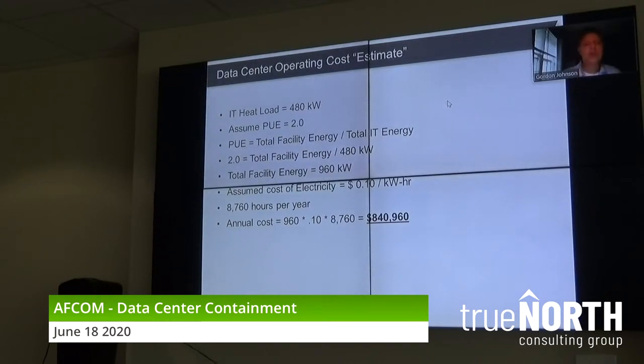So you also know how many hours there are in a year. So if you look at my final line, if you take your IT heat load, which was 480, multiply that by your PUE, so in this case, 960, times 10 cents a kilowatt hour times 8,760 hours in a year, that's the cost to operate this data center. And again, if you've provided me those numbers, if they're accurate, we can guarantee you're going to be within a thousand, couple thousand, you know, you're not going to be far off from the cost to operate your data center.